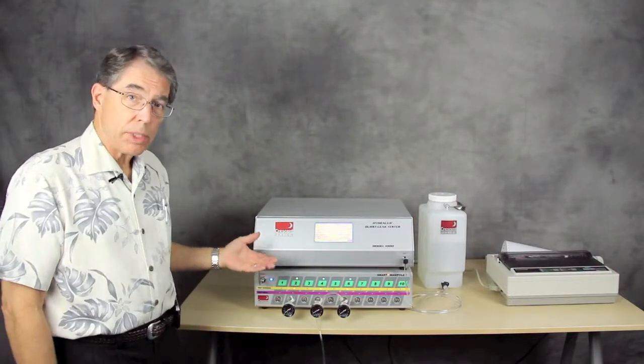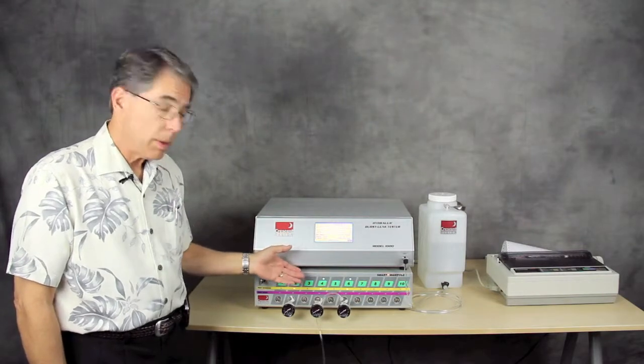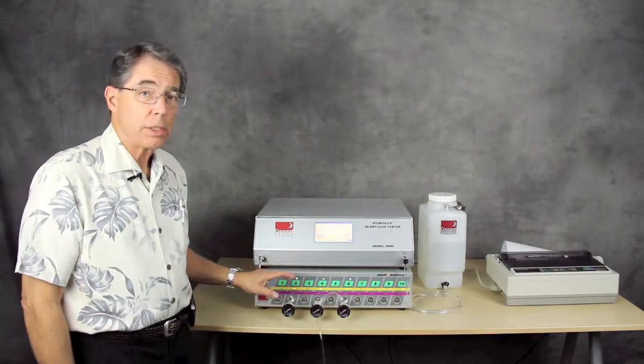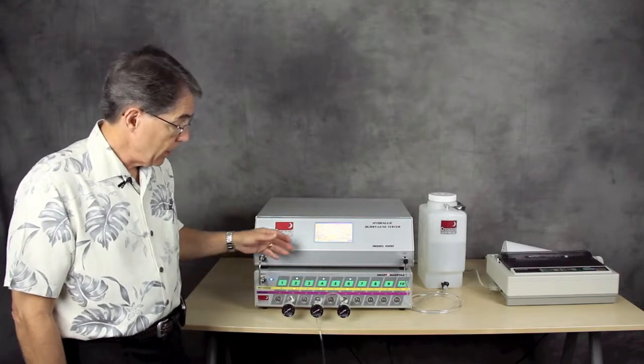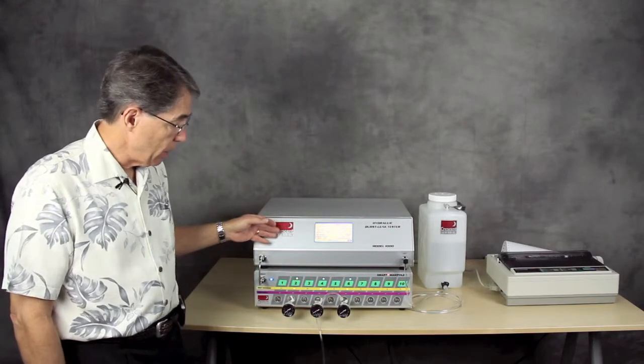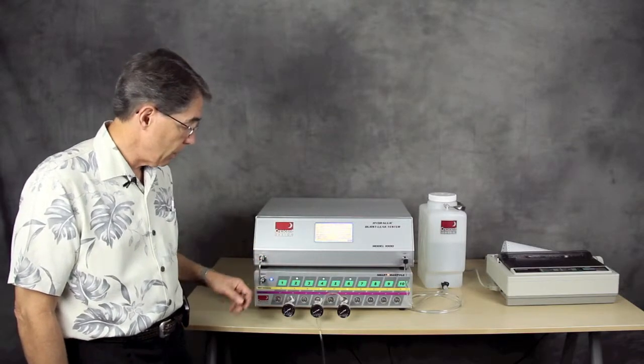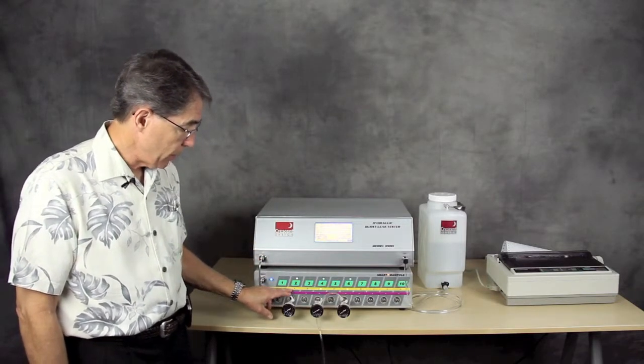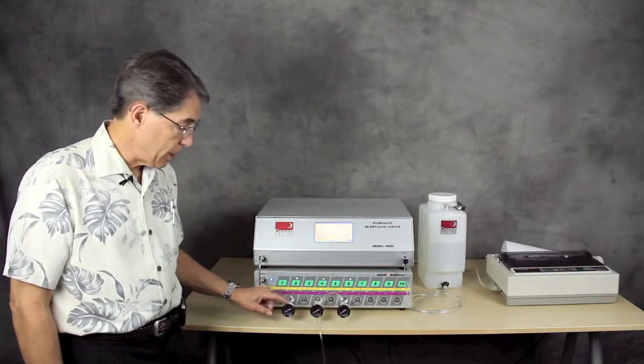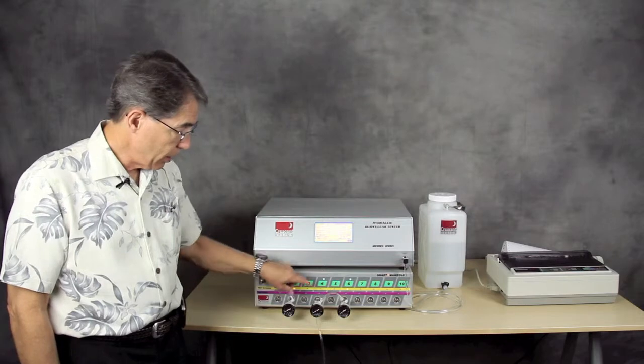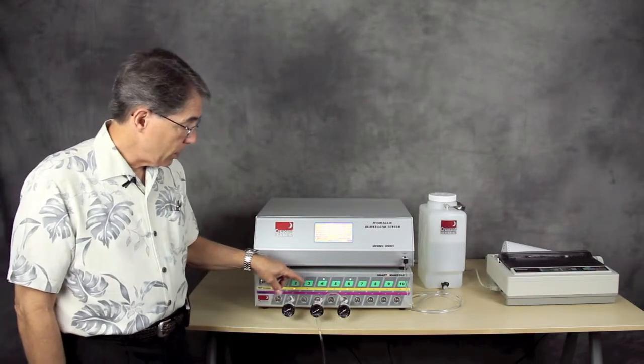So the system detected a burst. But at this point, it doesn't know which port has failed. So it is now going to prepare itself to do what we call the hunt. It's going to hunt for the test. So here you notice right now it's testing that port. And that port passed. It's not leaking. So it passed. It's now going to move on to this port and run the same test.